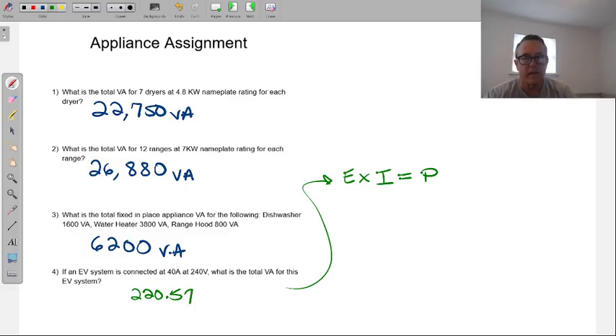But first, we need to know which one is larger, because we're getting information about the EV charger, meaning we don't just have to settle with what the code tells us. The code says the EV load shall be calculated at either 7,200 watts or the nameplate of the equipment. As I was mentioning yesterday with EV chargers, since you have such a wide range you can connect these to, you're going to be choosing that on site. You need to know what to do with that and how to approach it. So one, you need to be able to size the wires correctly, it's pretty easy as far as the steps go, but two, just to make sure we're code compliant.